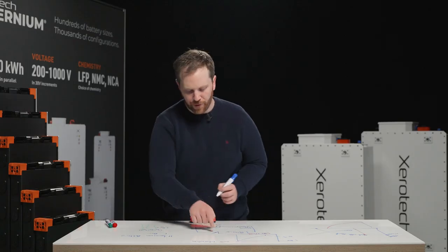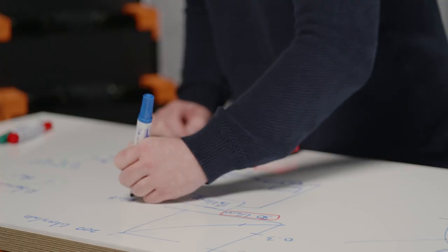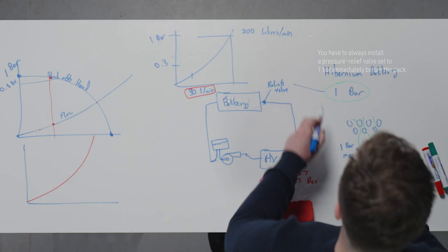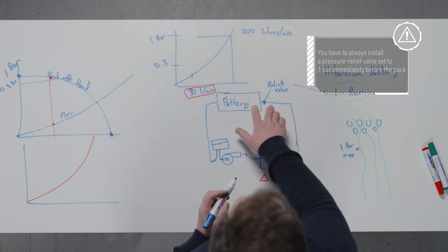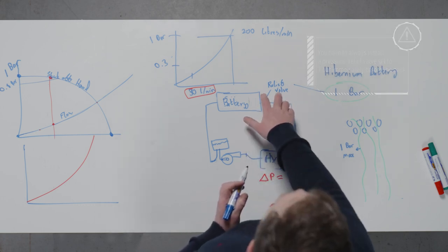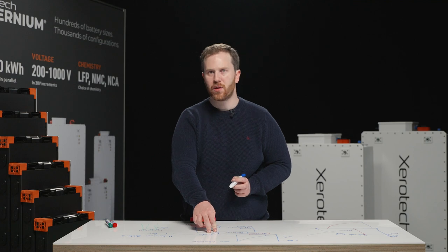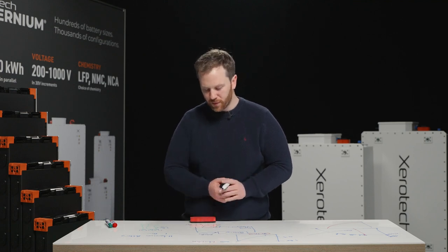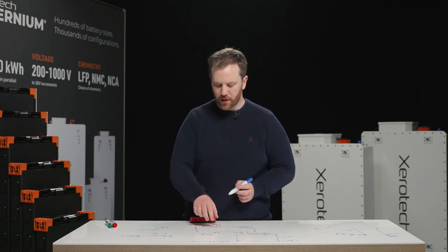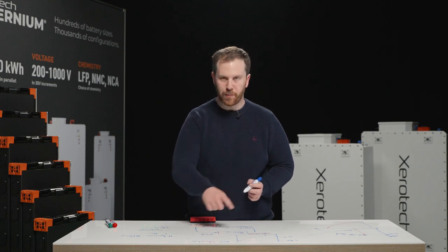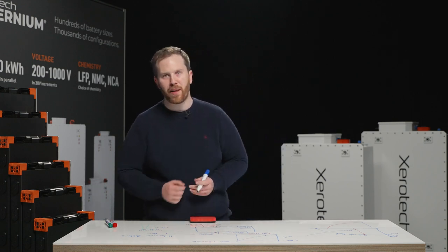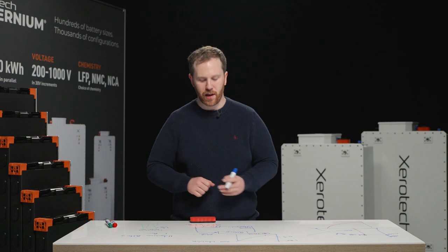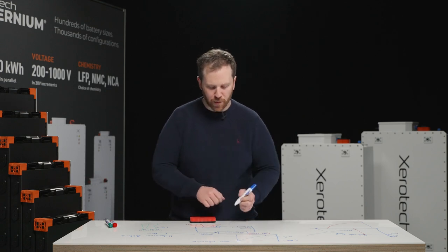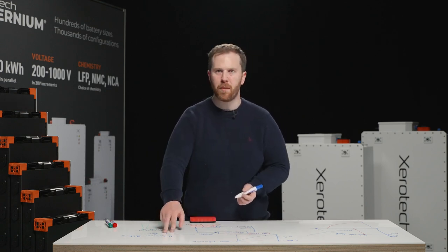You always want to have a pressure relief valve set to 1 bar to the maximum immediately before the pack. So the battery will never experience a pressure greater than 1 bar. And you might wonder how this could happen. In real systems, there's a lot more complexity than just heat exchangers and a simple loop. There may be flow balancing valves, shutoff valves, isolation valves, and it's rare that your pump is only going to be able to go to 1 bar.